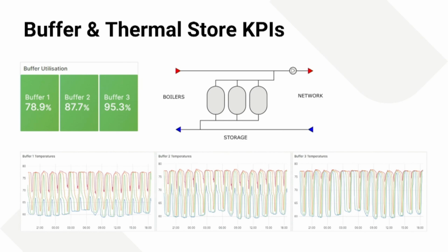Buffer store KPIs. What we were quite keen to do was to put a single metric on how well your buffer stores are loading and discharging, because it's quite a complex thing. You'll look at graphs and work it out. You can actually just put the sensor data through a fairly standard function, and it will give you the KPIs to allow us to spot when buffer stores are charging and discharging. If something goes wrong with sensors, controls, pumps, valves, and it stops loading and discharging, then they will go red, and you can attend to them.